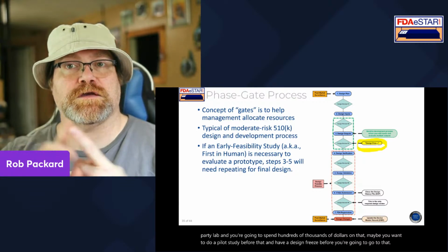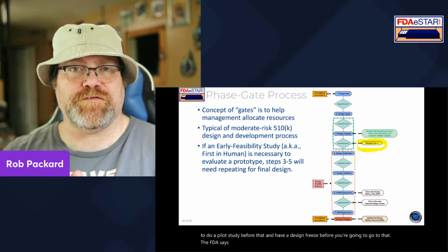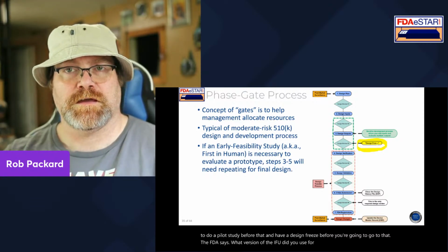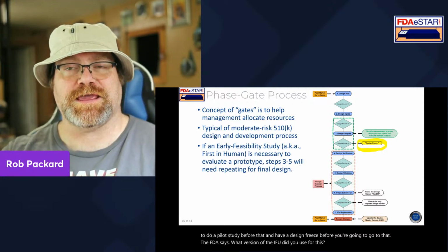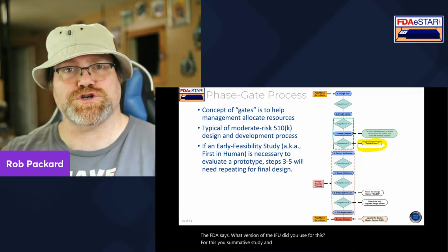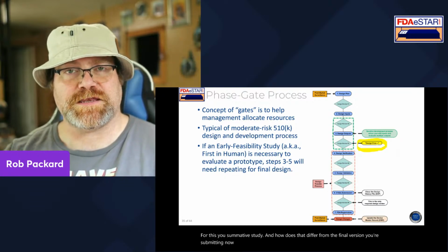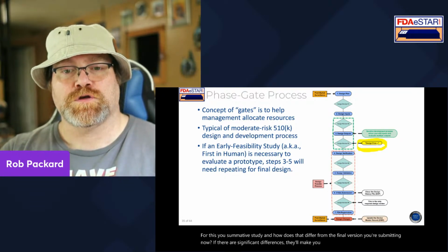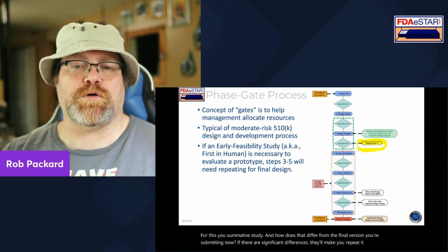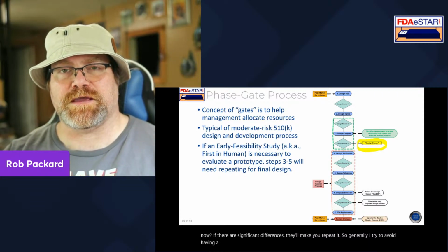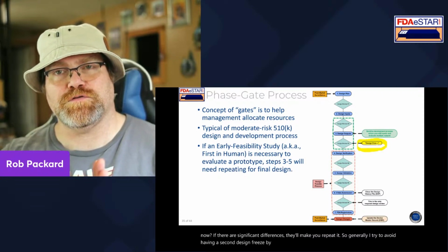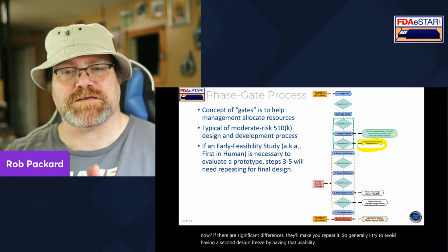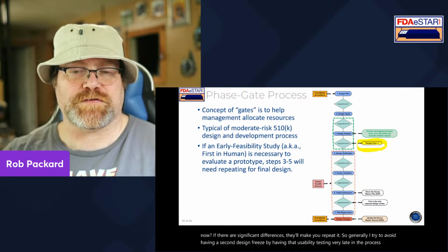The FDA says, what version of the IFU did you use for this summative study, and how does that differ from the final version you're submitting now? If there are significant differences, they'll make you repeat it. So generally, I try to avoid having a second design freeze by having that usability testing very late in the process after my IFU is finalized.